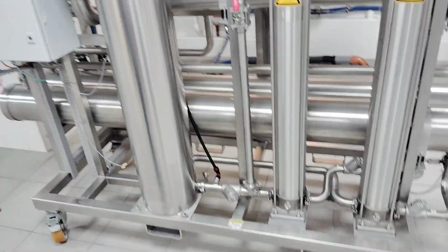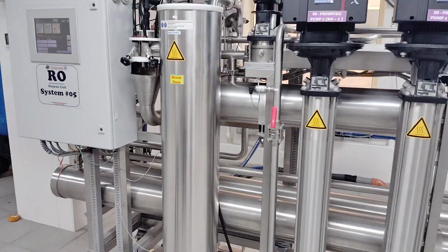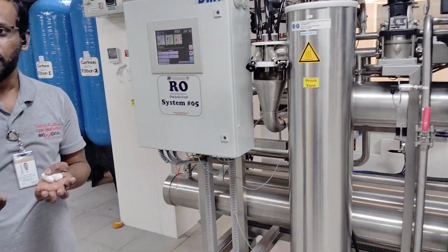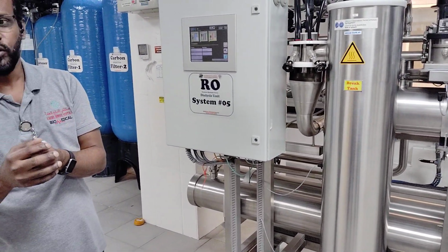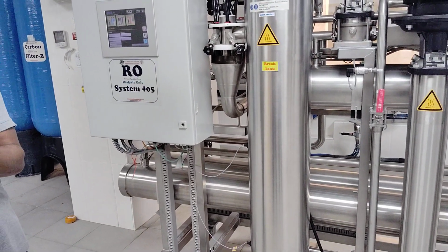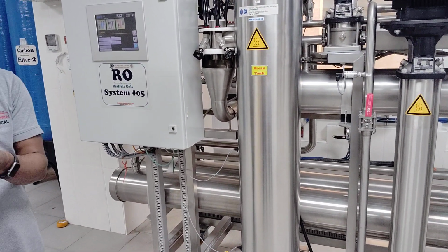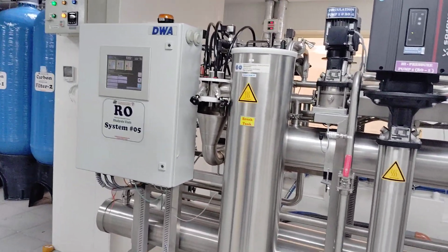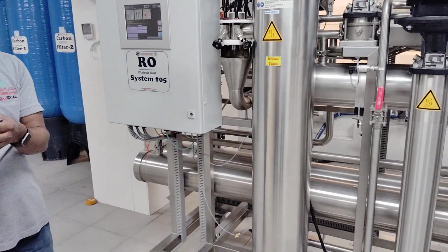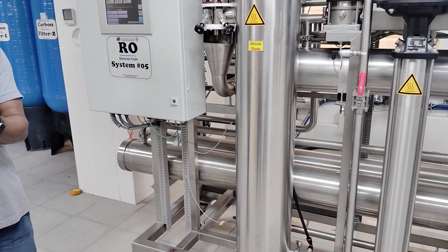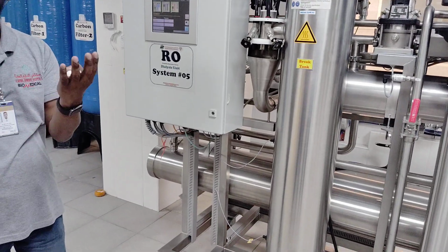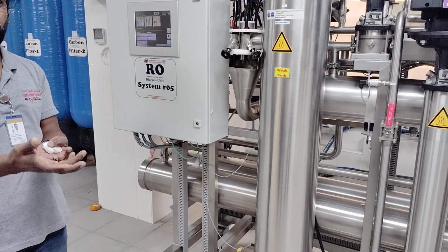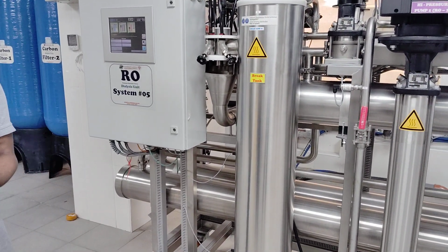The membrane is actually trying to take the water, and the water there will definitely contain endotoxin and bacteria. Maximum, it's trying to trap that endotoxin and bacteria. Endotoxin is like a dead bacteria. Normally there is bacteria in the water. Then we put some chemical or something, and we kill the bacteria. That is the time it forms the endotoxin. The dead bacteria become endotoxin. We take the dead bacteria count and the live bacteria count, these two we are taking.